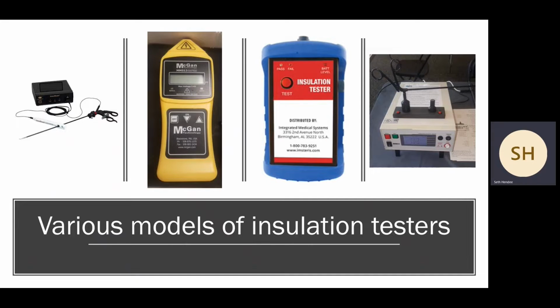There are various models of insulation tester out there, right? This is just a few. What I really think is interesting is the one that you see on the far left. That actually comes sterile. So the unit itself isn't, but that wand with the cord actually comes sterile so that it could be done immediately before the device is used on a patient. And I've got to say, that's a very interesting concept. And if you have a lot of problems, I can see an OR saying, I'm sorry, I'm not going to use a device until I test it myself.